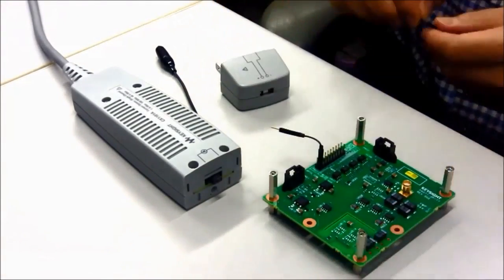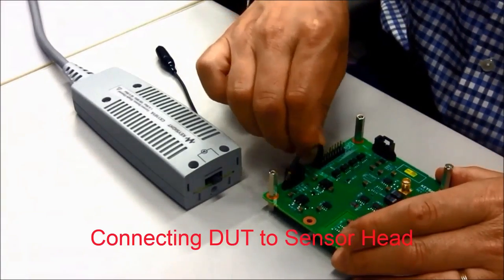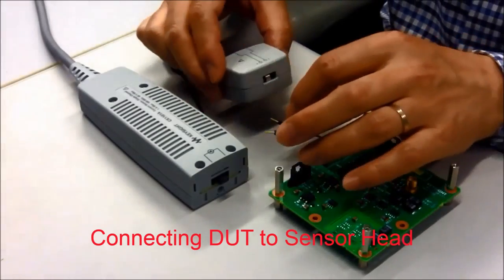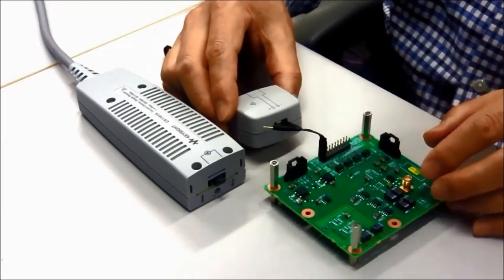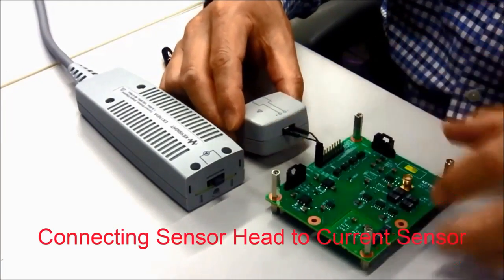This example shows the case where the DUT board has integrated current measurement monitor pins. In this case, the test lead sensor head provides an easy way to measure the current waveform.